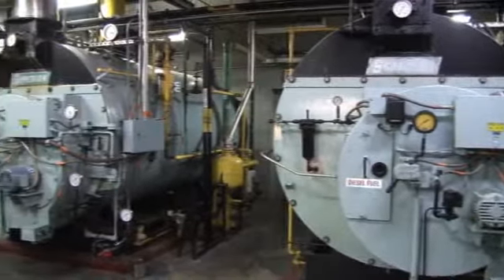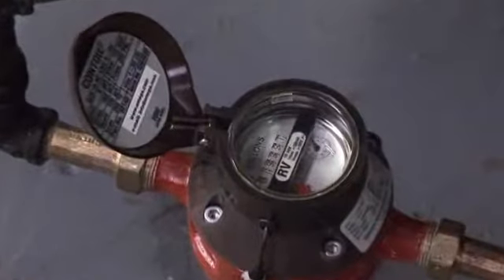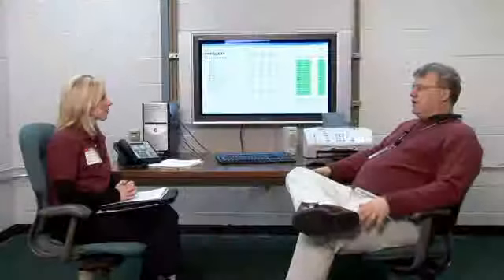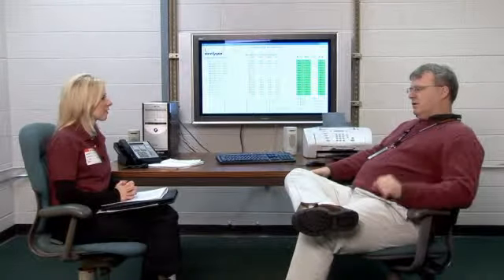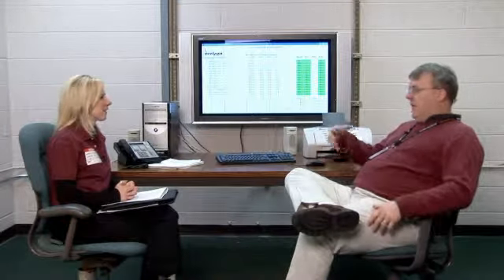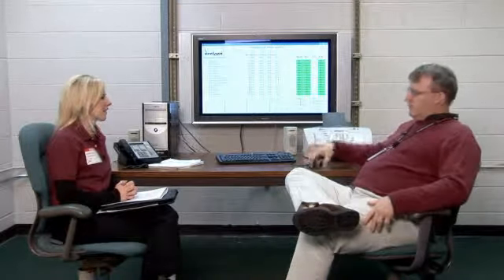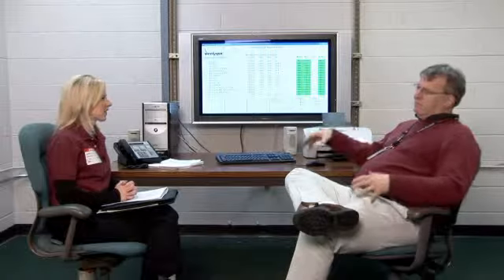In other words, we'll send alarms when a fuel level drops low in a fuel tank, the same way Unicenter would receive an alarm from a printer that ran out of paper. So by using Unicenter at the data center and using the Opto equipment connected to the network in the remote buildings, it enabled us to put the whole picture together.